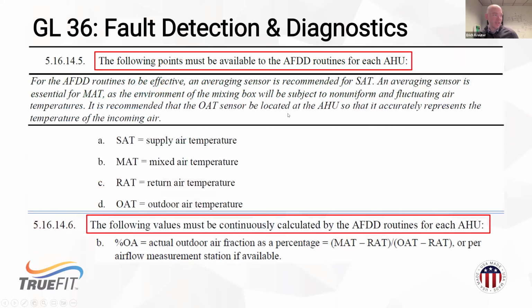And I'll come back to that Guideline 36, that this is the exact method that they want to run all of the fault detection for these high performance buildings off of. The benefit here is when we're actually producing airflow measurements with the airflow curve, and I have delta T, we're giving you two OA measurements, one from the performance curve, which would be the standard measurement. We'll run the delta T measurement, or the mixed air temperature equation measurement, in the background, and we want to see those be very close together.